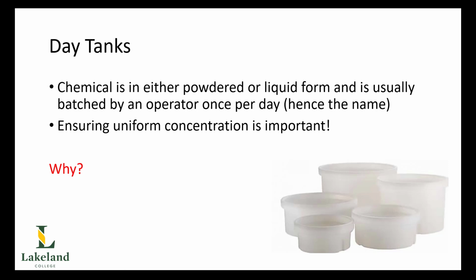Now, another disadvantage that's not really mentioned, and it is mentioned on the advantages, however, it says safer handling of the chemicals. Well, if you're handling it every day, is that safer than if you never had to handle it? I would disagree. Continuous pump tanks, you never have to handle the chemical. The water consultant rep does that for you. So in my opinion, that's a lot safer than the day tanks, even though they do state there is safer handling of the chemicals. The reason why they state this is because the chemicals are diluted with water. Hence, as a chemical, it's not as harmful to you as a neat or a concentrated one.